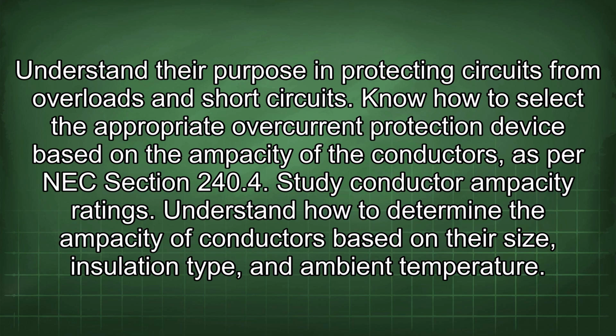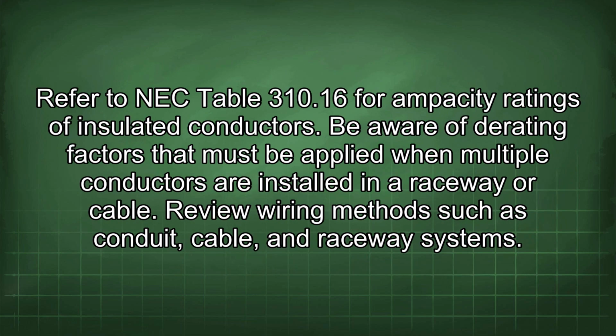Know how to select the appropriate overcurrent protection device based on the ampacity of the conductors, as per NEC Section 240.4. Study conductor ampacity ratings. Understand how to determine the ampacity of conductors based on their size, insulation type, and ambient temperature. Refer to NEC Table 310.16 for ampacity ratings of insulated conductors. Be aware of derating factors that must be applied when multiple conductors are installed in a raceway or cable.